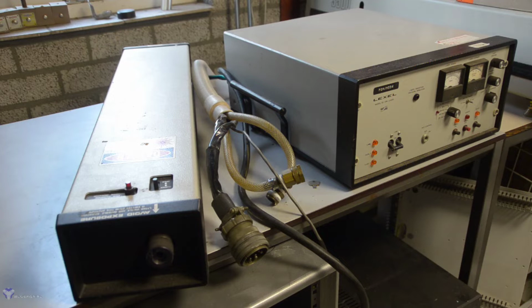Now, the reason argon lasers are not very popular anymore is because of their low efficiency. Because even with this 1 watt multi-line output, this laser requires several kilowatts on the input. So that's an efficiency well below 0.1%, and that's not very convenient to work with. It's a very good water heater, and these have been phased out in favor of solid state lasers, which require a lot less power on the input, are more stable, and are easier in operation.